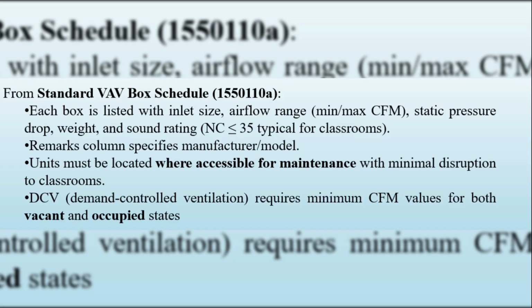Scheduling and acoustic limits. Each VAV box is detailed in the project schedule. That schedule shows the inlet size, the airflow range, static pressure, weight, and the sound rating. Classrooms need a quiet environment, so boxes can't exceed NC 35 under normal conditions. The schedule also records which manufacturer and model is used, and it ensures the units are placed in spots that are accessible for maintenance without disrupting class. For demand-controlled ventilation, minimum airflow values are set for both occupied and vacant conditions, so the system balances air quality with energy savings.